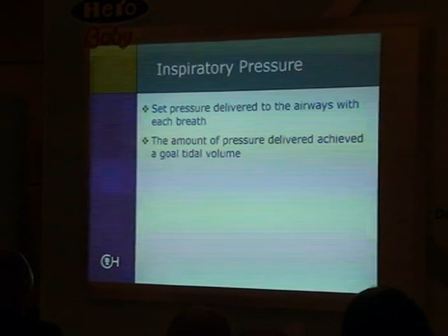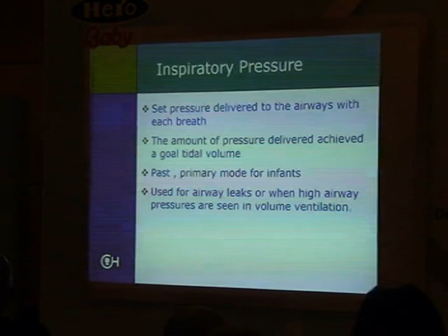If it's a volume mode, then you want to monitor the pressure as much as you're monitoring your volume in the pressure modes. In the past, this was predominantly how we always ventilated infants and babies. And in many places in the world and in the United States, pressure modes is still how we, most of the time, ventilate our babies. And we'll be talking a little bit more in the next coming days about the use of volume modes, and volume limiting and volume guarantee, and how that might be beneficial, knowing that volume, not pressure, is what causes the injury in the lungs. However, when you have airway leaks, if your endotracheal tube is a little bit too small, or when you're getting very high pressures because of your lung compliance, sometimes pressure ventilation is easier and safer to use than volume ventilation. So we'll also be talking about those challenges in trying to determine with each mode.